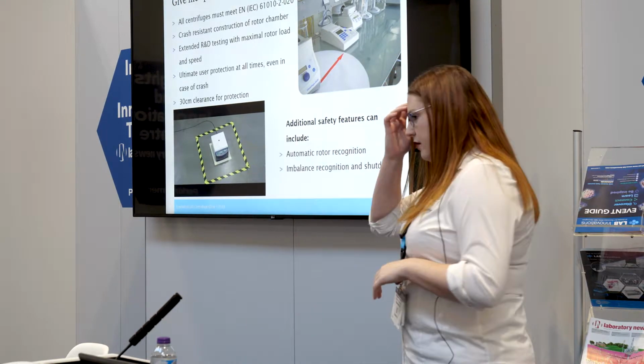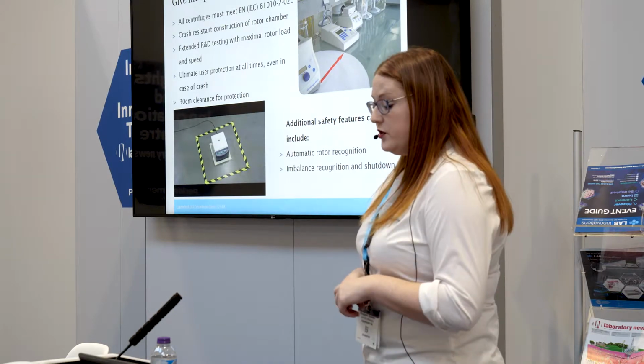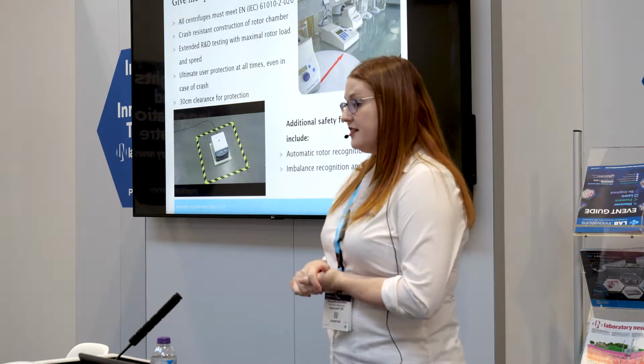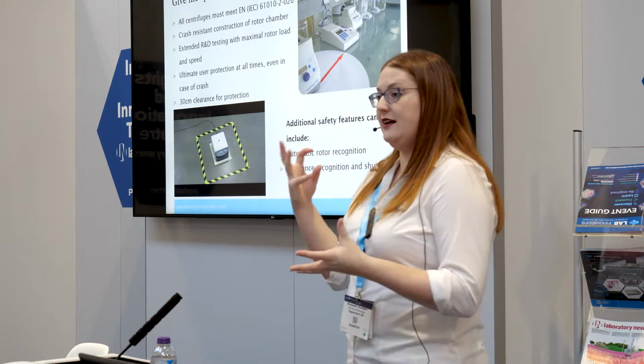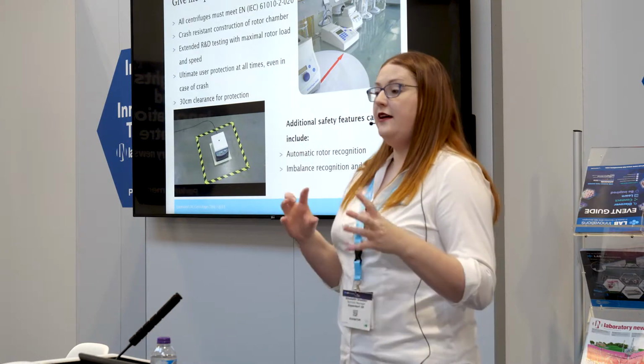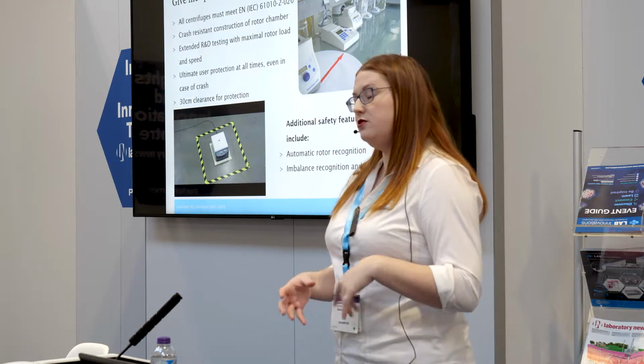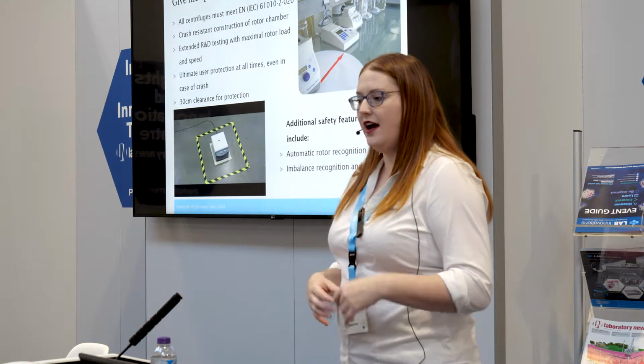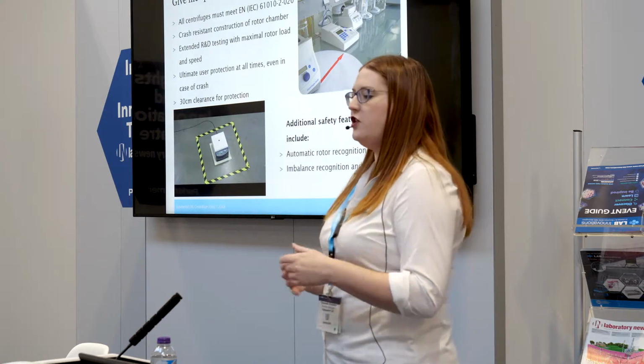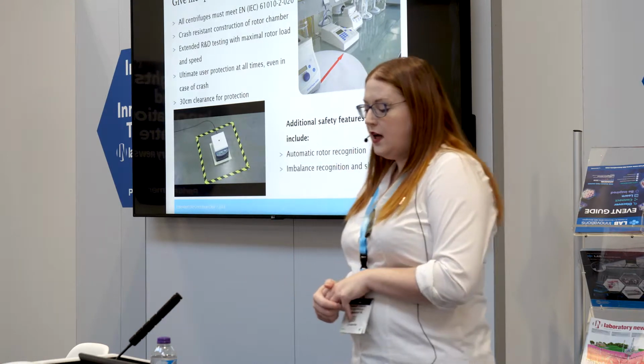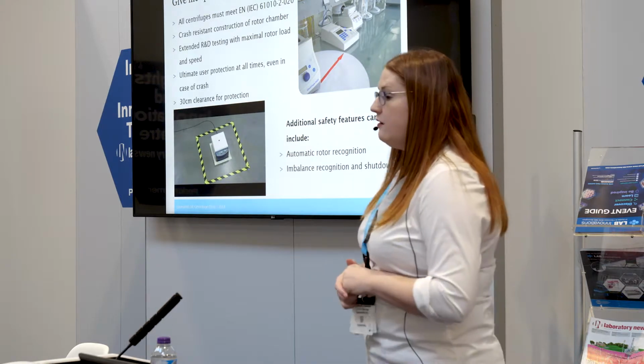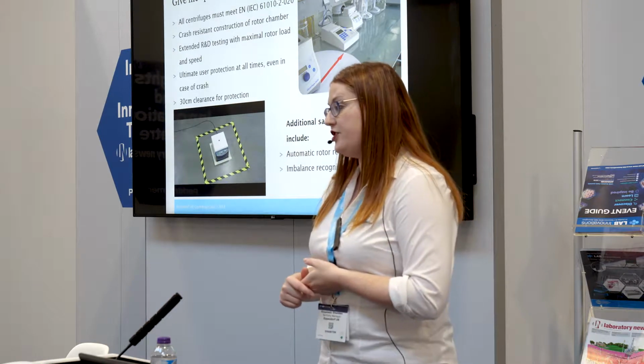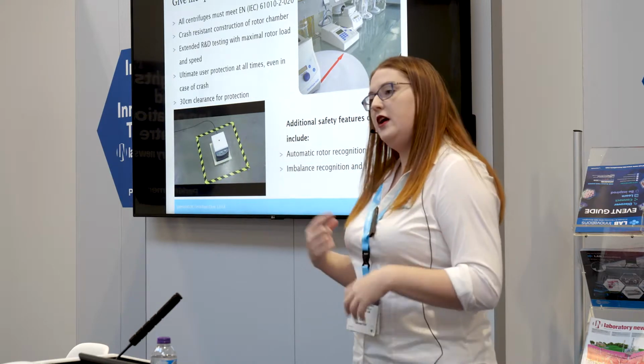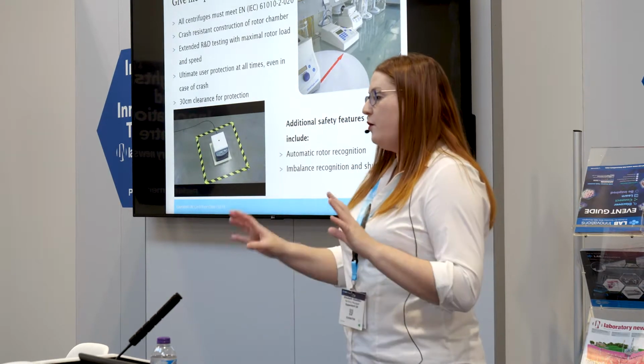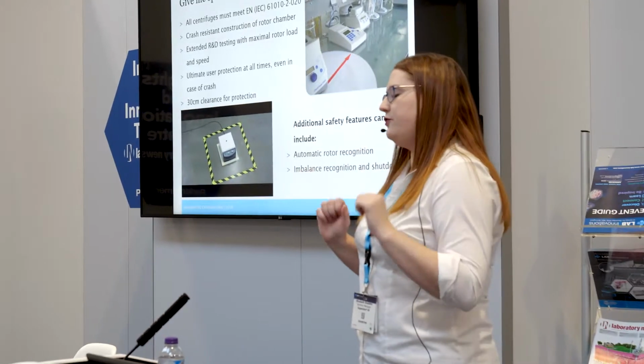Other safety features that most centrifuges nowadays include are things like automatic rotor recognition. Different rotors will have different restrictions in terms of the speeds and the volumes that they can hold, and the centrifuge will know what those are and automatically put restrictions on it so that you can't spin it too fast, for example. And most of them nowadays also have automatic imbalance recognition shutdown. So the centrifuge will start to spin up. If it's not balanced, it shuts itself off before larger forces can build up, and it gets unsafe.